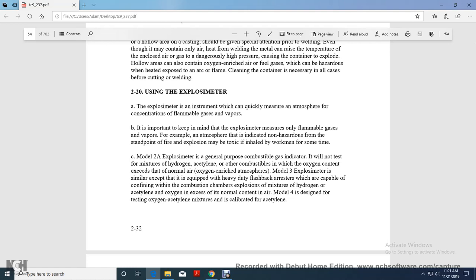2-20, using the explosimeter. An explosimeter is an instrument which quickly measures the atmosphere for the concentration of flammable gases and vapors. It's important to keep in mind that the explosimeter measures only flammable gases and vapors. For example, an atmosphere that indicates no hazard from the standpoint of fire or explosion may be toxic and may be inhaled by the workman for some time. The Model 2A explosimeter, a general purpose combustible gas indicator, will not test for mixtures of hydrogen, acetylene, and other combustibles, or where the oxygen content exceeds that of normal air, an oxygen-rich atmosphere. The Model 3 explosimeter is similar except that it is equipped with heavy-duty flashback arresters, which are capable of confining combustion to the chambers when exposed to a mixture of hydrogen and acetylene.